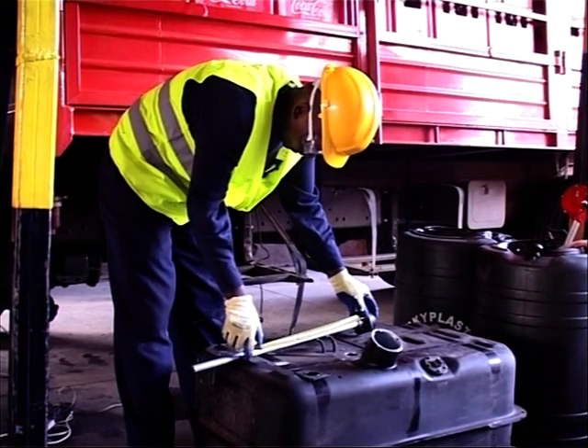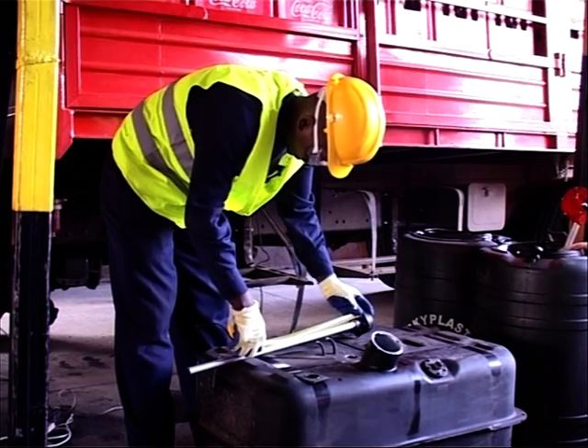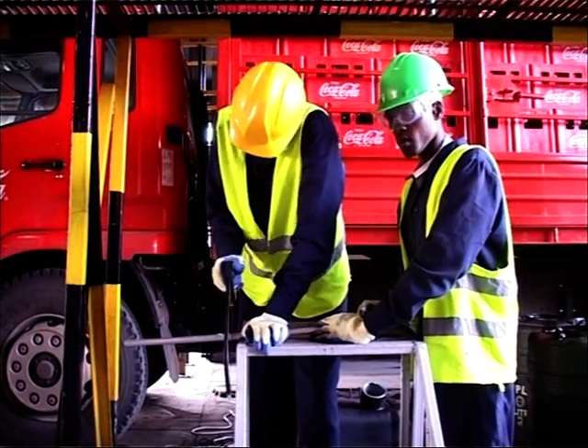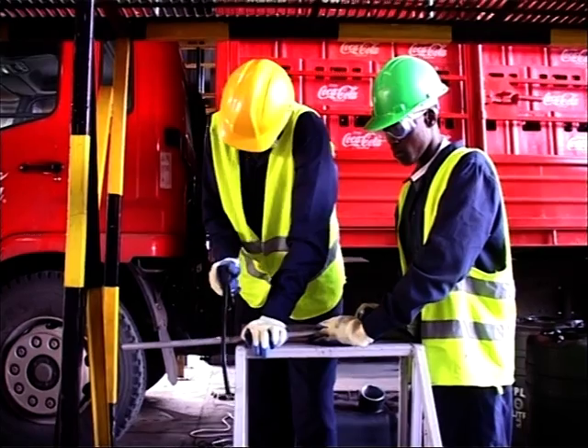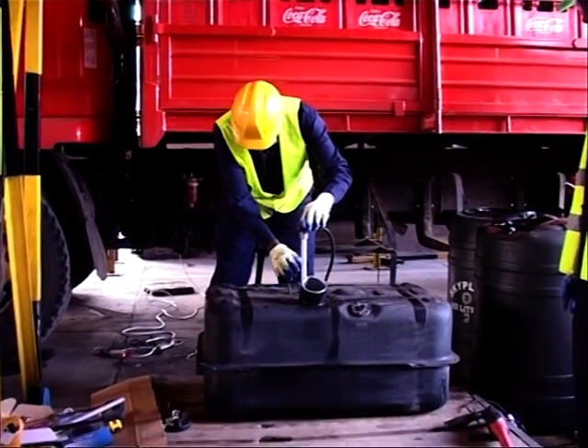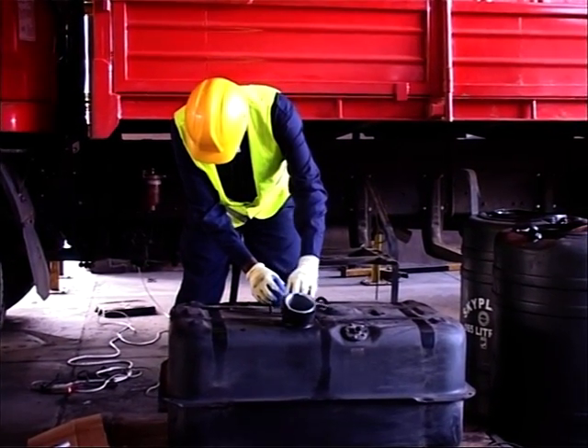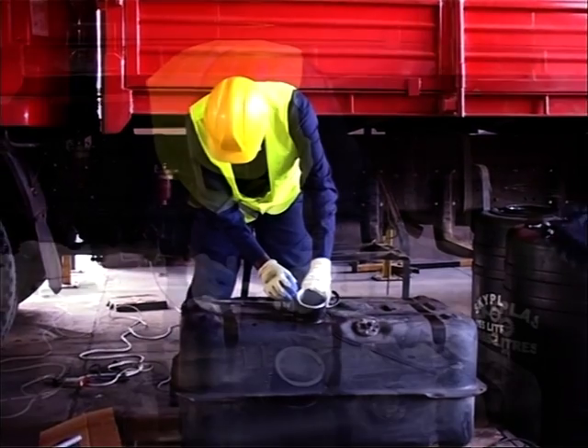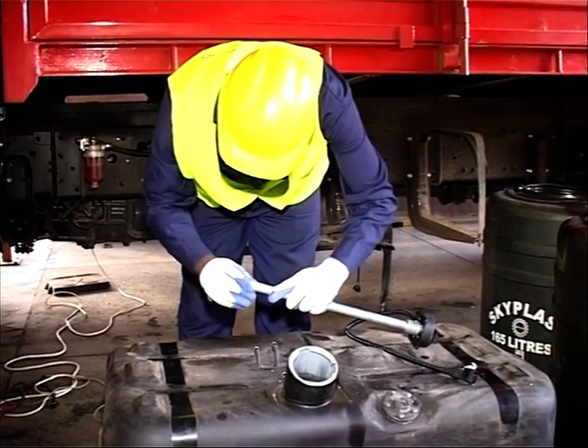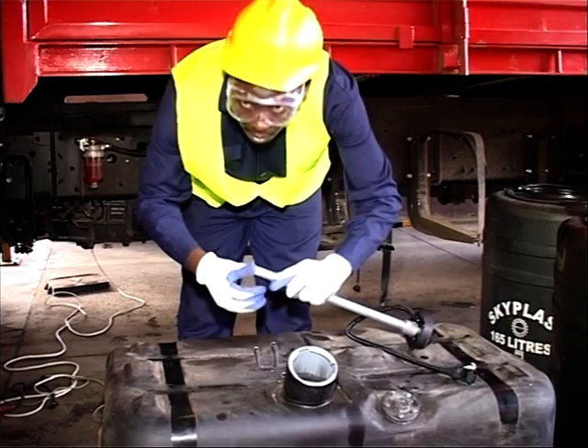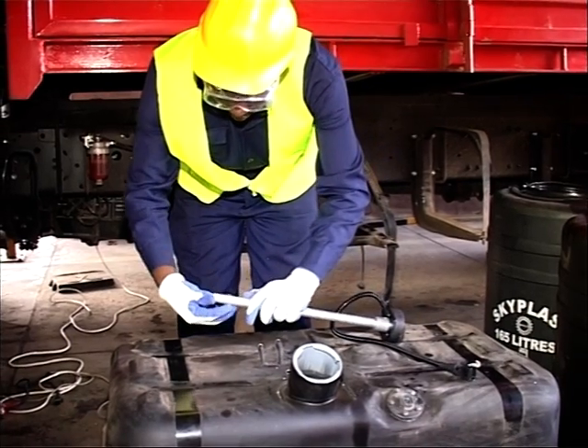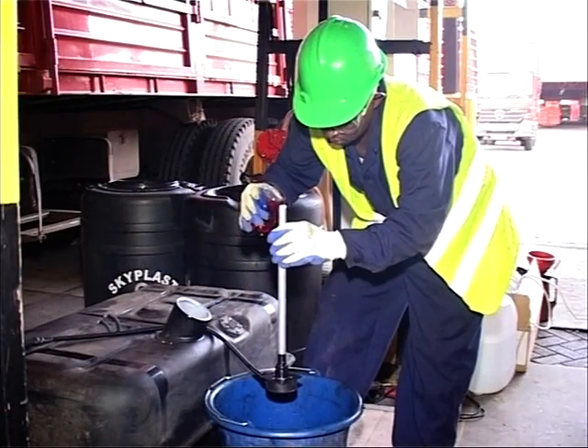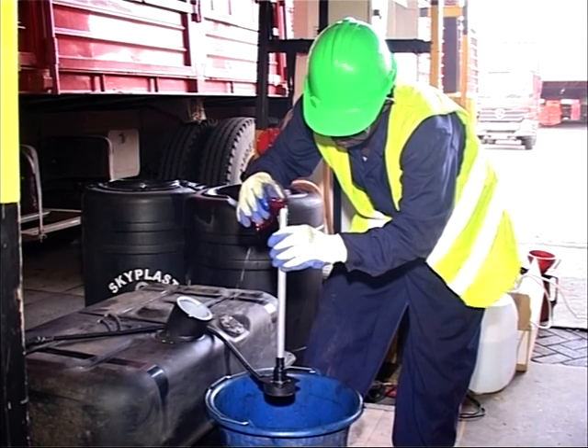The level sensor comes in a variety of lengths. So at this point you have to cut the level sensor to a suitable length that will be able to work in the tank. After this, you put a sealant at the end of the tube core. This one prevents moisture buildup inside the sensor. We go now to calibrate the sensor itself.